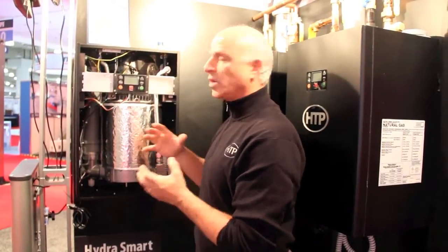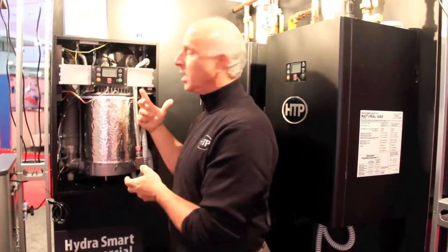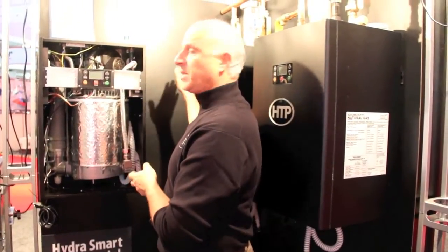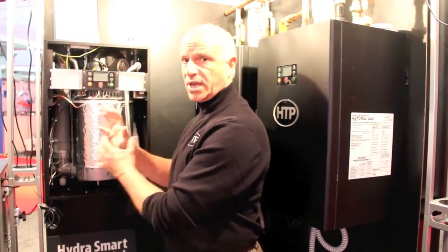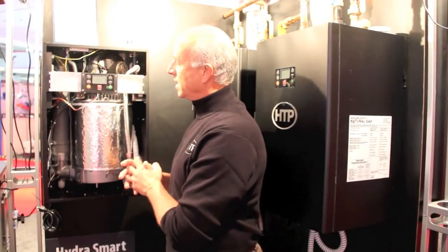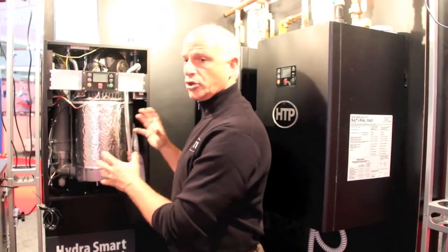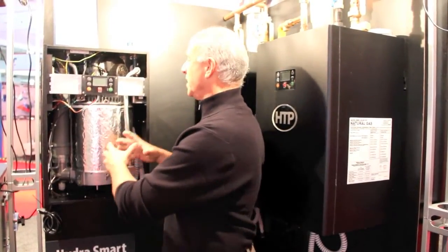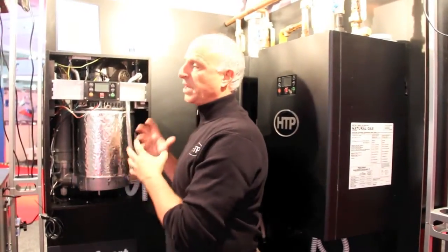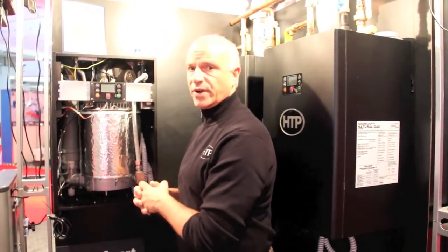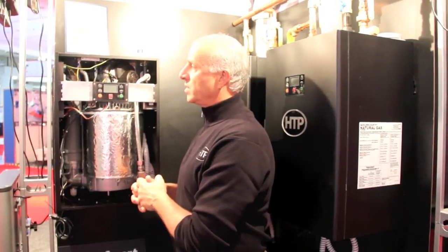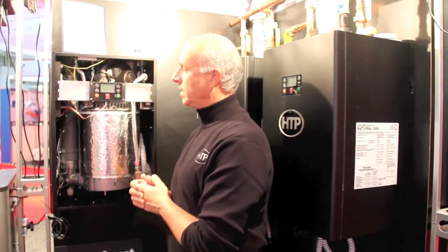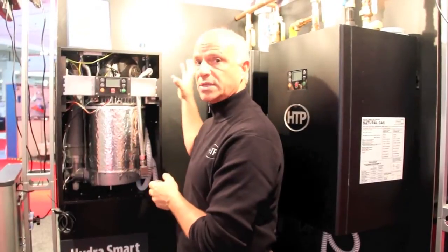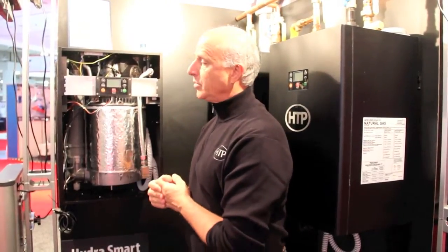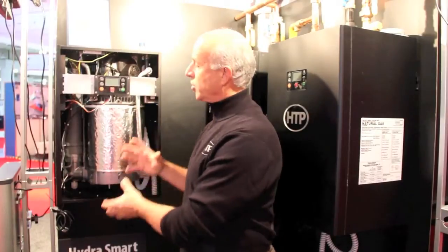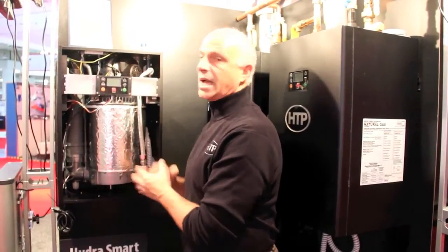That's really unique, because if you got recirc in a building, we're only going to flow through one of them and keep the other ones off. It'll also rotate based on time how these are used, so each unit will get equalized time. So instead of storing a lot of water, having big tanks, this can be fit into a very small area with this single penetration and having the ability to manifold your vent system, manifold your piping. You can put a lot of power in a very small area. You can hook them up to storage tanks. There's just a lot you can do.